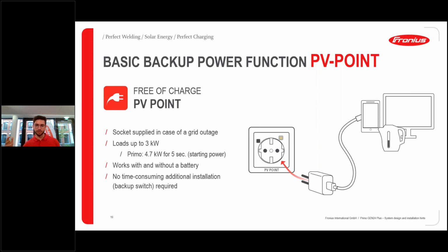And then you can charge your devices, you can plug in your refrigerator and so on. And very important to know is it's working without any battery. So it's not necessary to have one installed in the system, but you need to make sure that the PV Point is really only working if the grid is gone. So if the grid is here and the inverter is producing and feeding into the grid, the PV Point will be deactivated. So you cannot permanently plug in your refrigerator, for example. It's not working until the grid is gone. So very important to remember that. And the good thing is, of course, there is no time-consuming additional installation. It's really just a single phase cable, an RCD, and the wall socket, and that's it.